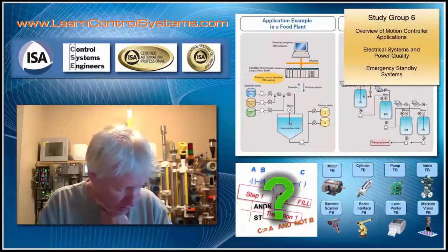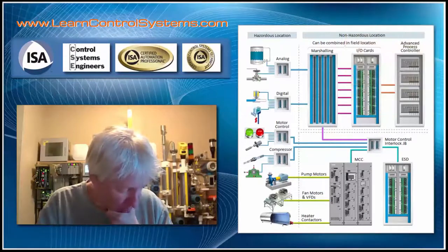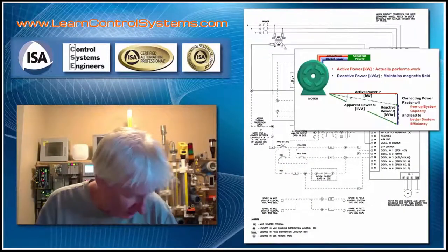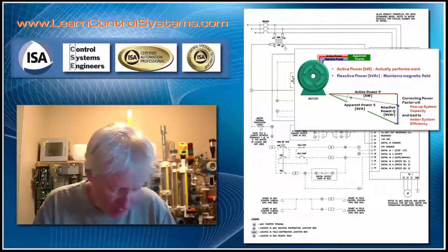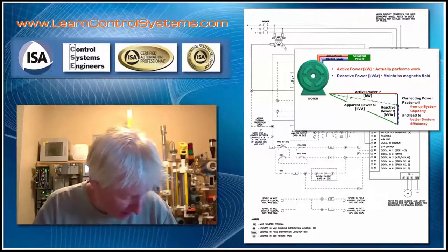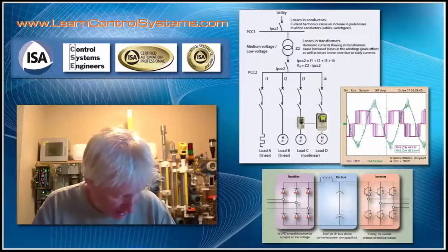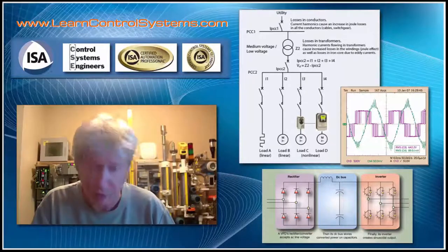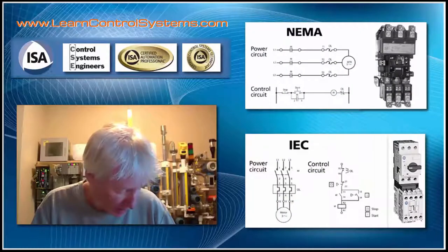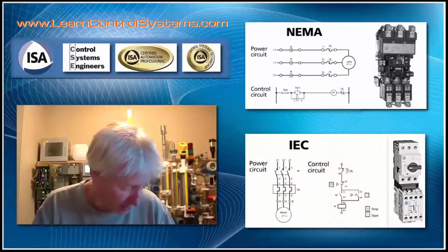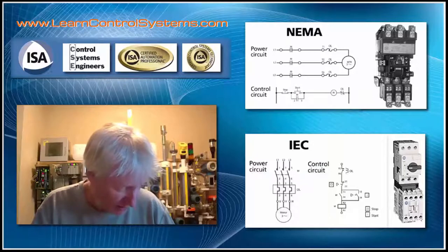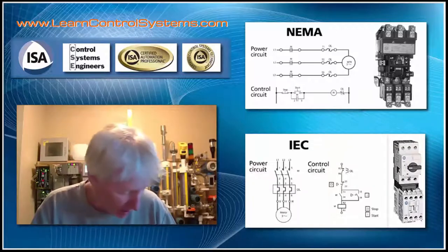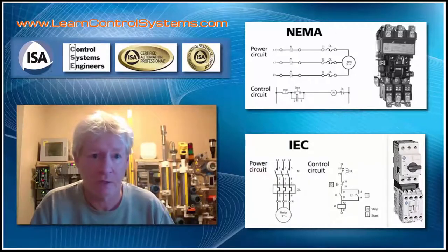We'll cover motor controls and logic functions: the fundamental starter, what the code says about starters, logic functions for controlling motors, frequency drives and how they work, soft starters, why we use them, and power factor correction. We'll discuss harmonic neutralization, IEC and NEMA standards, how to install and size starters, how to protect our motors and processes. For critical processes, we'll put a bypass contactor beside the frequency drive so if it fails the process keeps going.